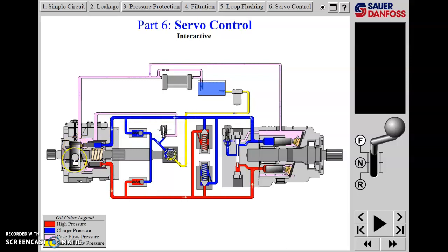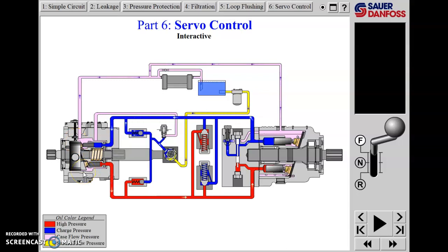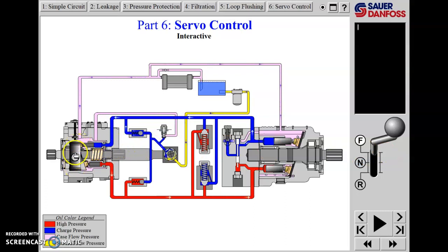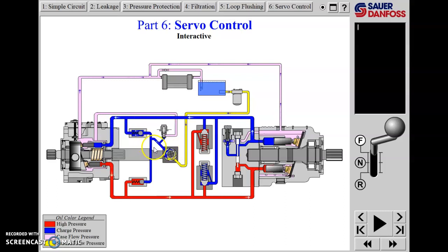This particular pump uses one double-acting servo; the one in the main shop uses two single-acting servo cylinders pushing on linkages on either end of the swash plate, but the end outcome is the same. We're removing the mechanical feedback of the swash plate pushing back on the linkage, so the operator just operates a pilot control and uses hydraulics. The source for that pilot oil — or servo supply, as it may be called in European systems — is generally the charge supply.